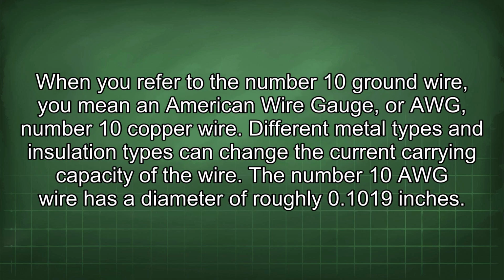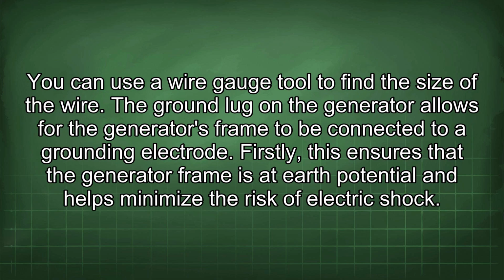When you refer to the number 10 ground wire, you mean an American Wire Gauge, or AWG, number 10 copper wire. Different metal types and insulation types can change the current carrying capacity of the wire. The number 10 AWG wire has a diameter of roughly 0.1019 inches. You can use a wire gauge tool to find the size of the wire.